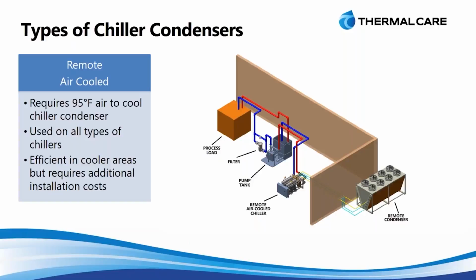And what that allows us to do is leave that chiller indoors. So one, you can have access to it while we're still ultimately rejecting the heat of the system outside. So we're not putting any sort of heat load on the HVAC system. We're not building up heat in the facility. But now we have the chiller inside, so we don't have to send any water outside. So now we've avoided the glycol issue.